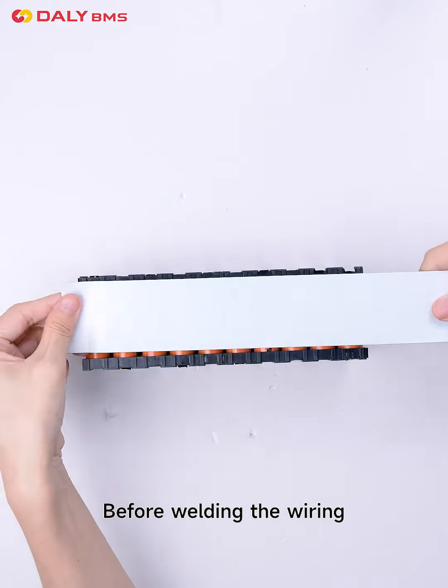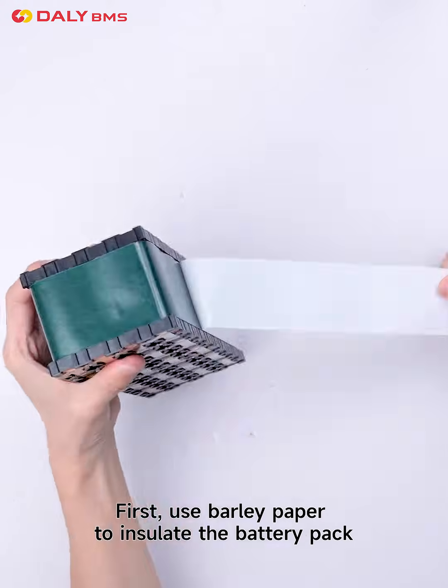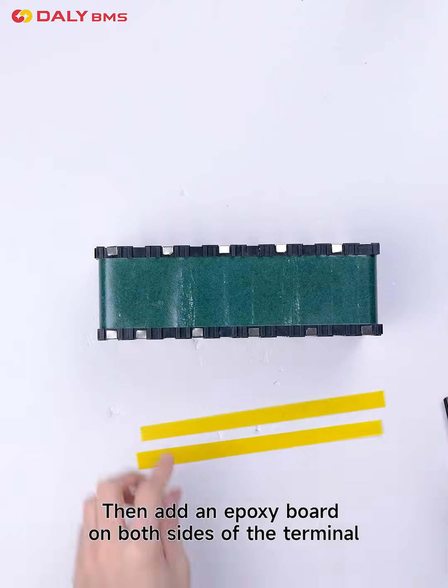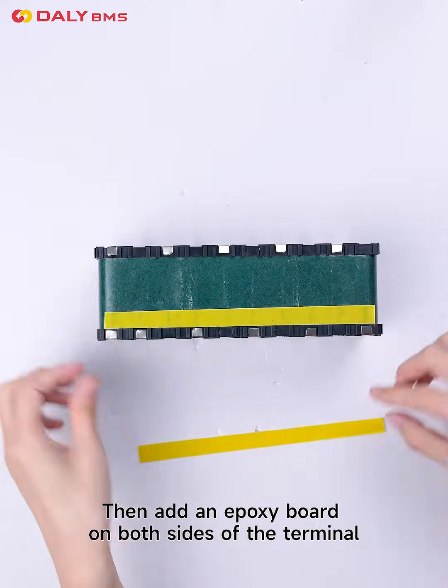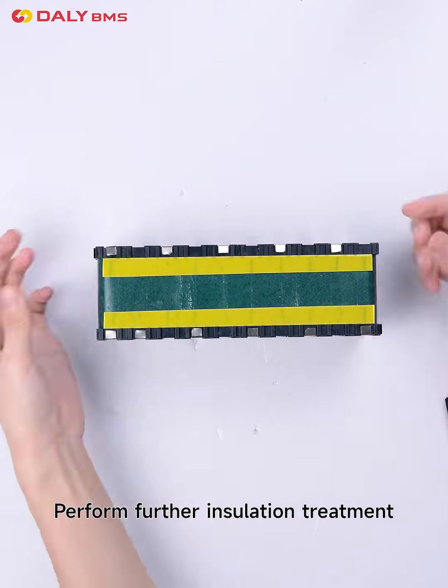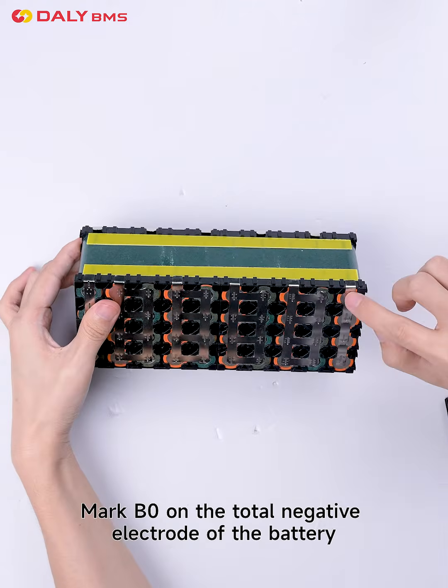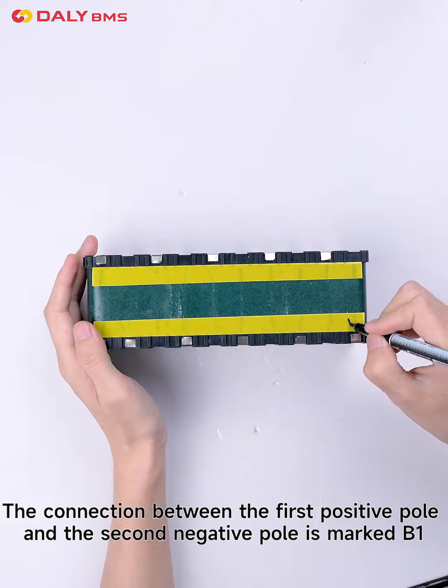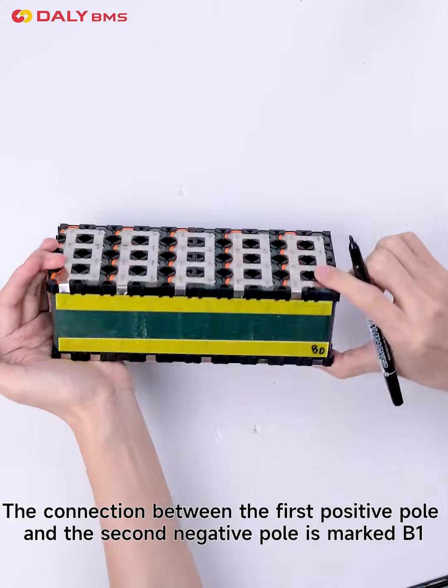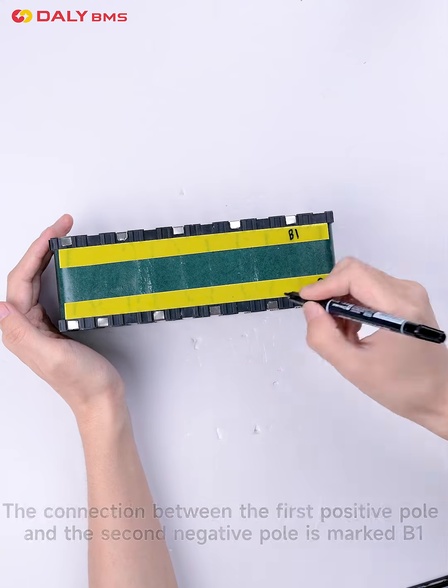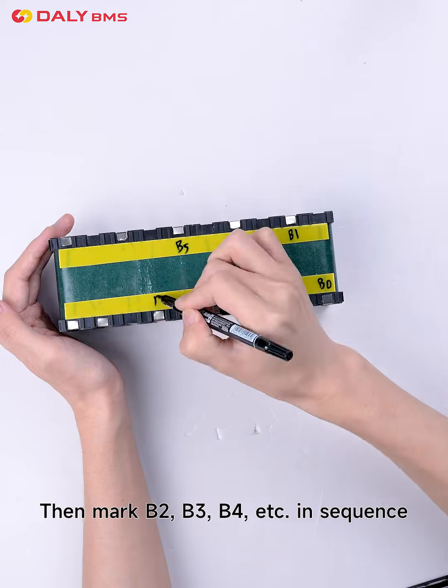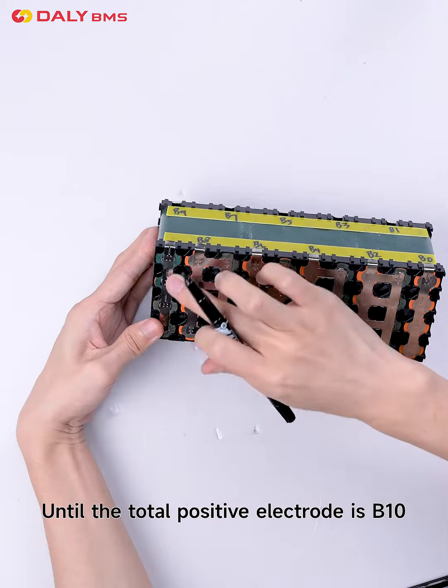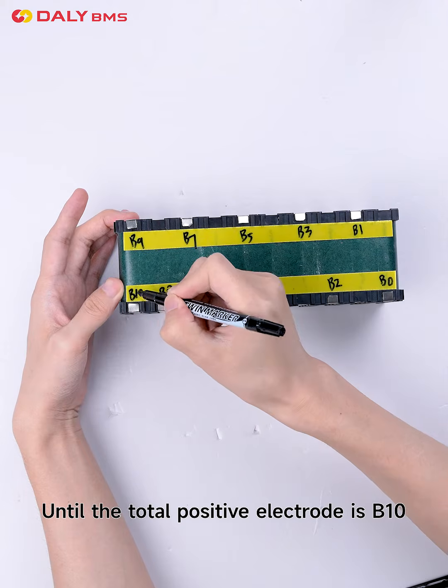Before welding the wiring, first use poly paper to insulate the battery pack. Then add an epoxy board on both sides of the terminal. Perform further insulation treatment. Mark B0 on the total negative electrode of battery. The connection between the first positive pole and the second negative pole is marked B1. Then mark B2, B3, B4, etc. in sequence, until the total positive electrode is B10.